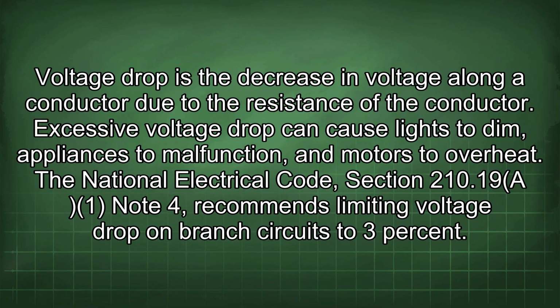Voltage drop is a decrease in voltage along a conductor due to the resistance of the conductor. Excessive voltage drop can cause lights to dim, appliances to malfunction, and motors to overheat. The National Electrical Code, Section 210.19(A) Informational Note 4, recommends limiting voltage drop on branch circuits to 3%.